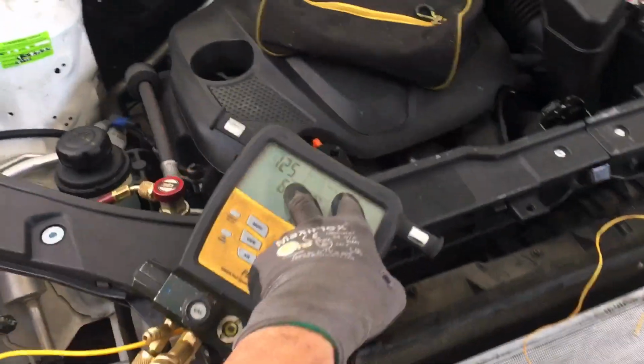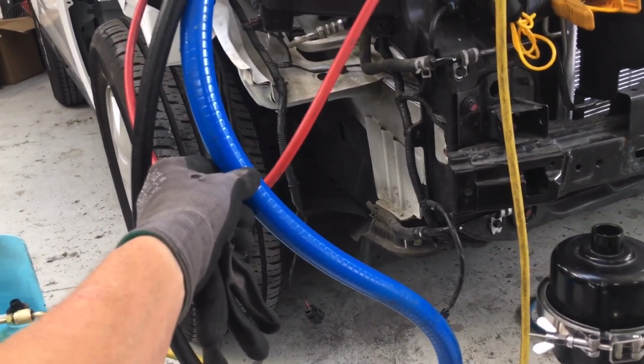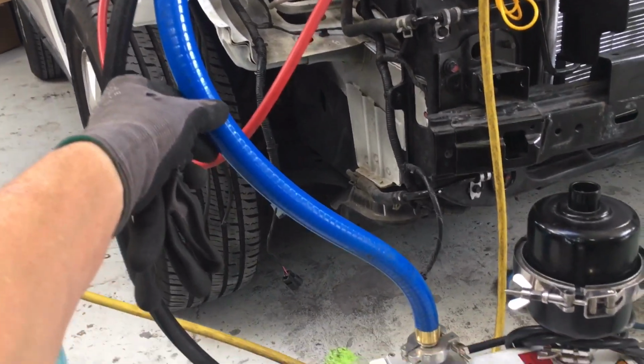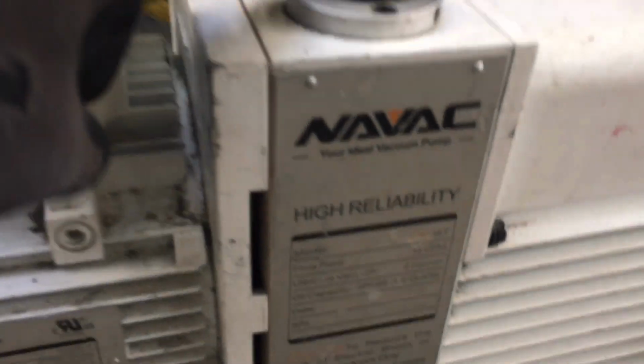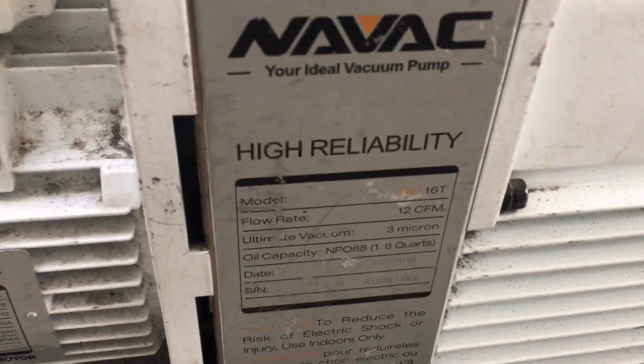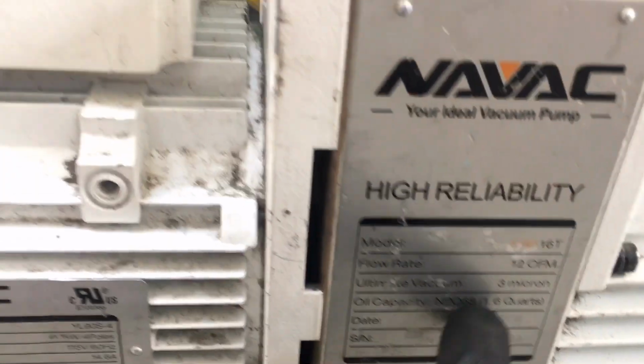I pulled this down to 125 microns using the Navac 12 CFM pump with a 3/4 inch vacuum-rated silicone hose. For those who want the model number, this is the 16T, rated down to 3 microns.